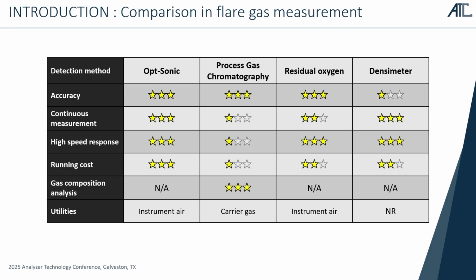And this is a table comparing some technologies commonly used in flare gas measurement. These are the items to be compared. I'll try to explain the Opt-Sonic sensor first. Accuracy is about 2% for flare gas. This is a continuous measurement, and since we use a physical sensor, no calibration is required in the field. There is no need to calibrate the sensor for more than 10 years. So continuous measurement is very good for this sensor, and it has high-speed response, T90 within 5 seconds.